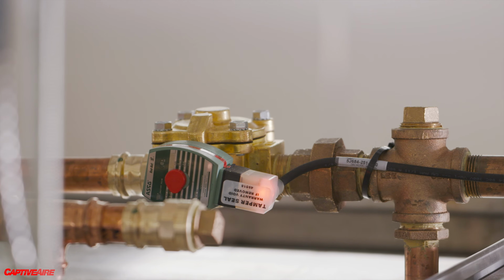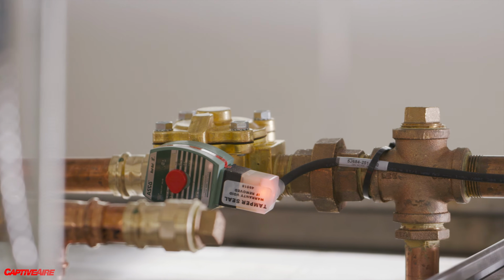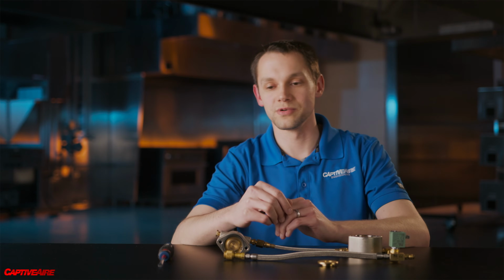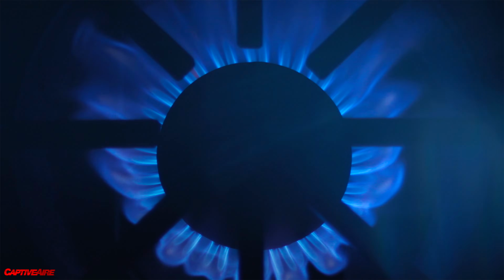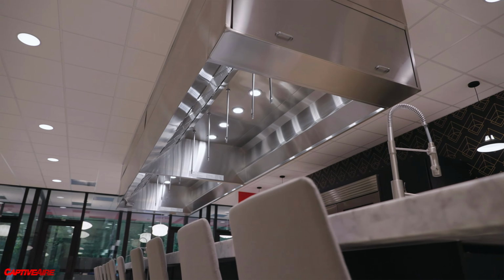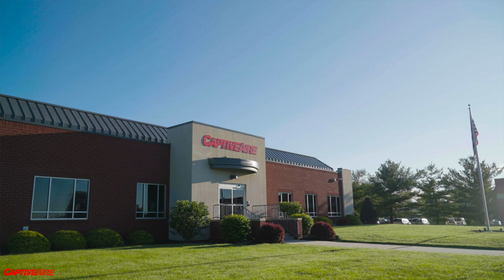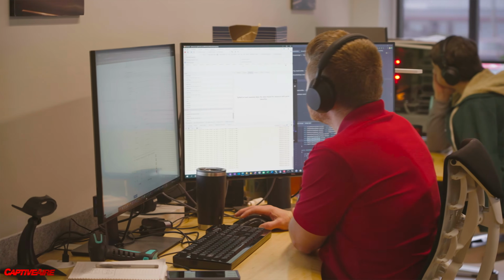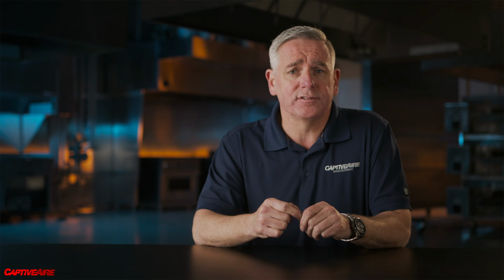So we can become intelligent to figure out what's actually happening in the system. So we can see if they're fully wired and present. And if not, we produce a critical fault that will shut down the appliances. This is called electronic supervision. And these faults can be monitored not only locally at the kitchen hood, but also remotely. So an engineer halfway across the country may be able to detect and even diagnose a fault before somebody in the building. So there's a lot of monitoring that goes on.